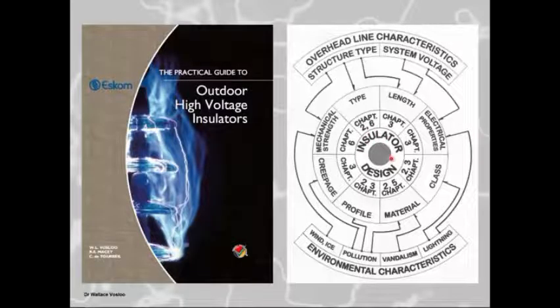If you want to design this insulator, what must you look at? What influences that insulator's design? And then further, where in the book must I go and look for it? For instance, if you want to look at the insulator's length, which is normally governed by the structure type, you could go and look at chapter 3, and there's everything about the length, but the length is also determined by the system voltage.